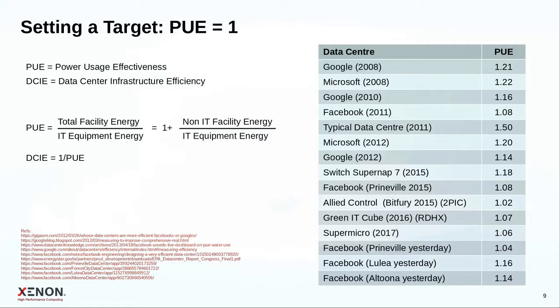Over time, organizations have been trying to drive that down. Google made big progress, going down to 1.1. A commercial data center by Switch claimed to have 1.18, for example. Facebook, in 2015 at the Prineville data center, claimed to have 1.08. It seems like for large commercial data centers we're now in the single digits for overhead in terms of cooling and energy. The standout is probably this Allied Control data center, a fully immersion liquid-cooled data center - I'll talk about that technology in a second - built for a large blockchain provider, essentially cryptocurrency. They're running with a power overhead of only about 2%, which is quite an achievement.